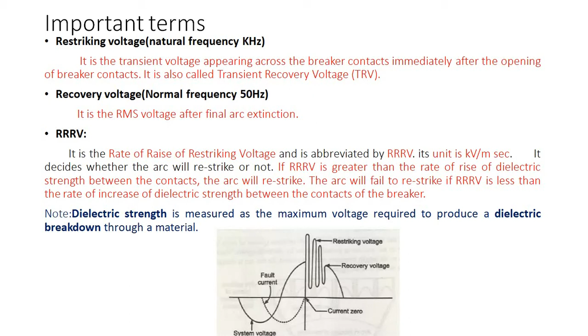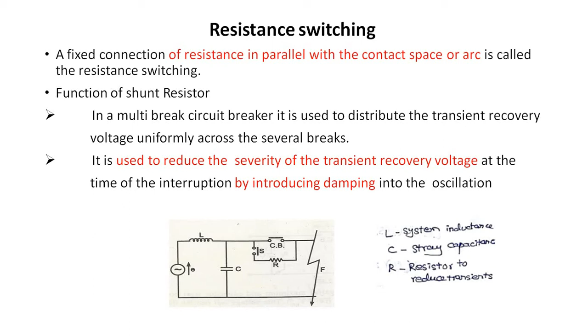Next point, resistance switching. A fixed connection of resistance in parallel with the contact space or arc is called resistance switching. Shown in the figure, the circuit breaker has a fixed contact and a moving contact, and in between, the resistance is connected in parallel. Function of the shunt resistor. The first point, in a multi-break circuit breaker, it is used to distribute the transient recovery voltage uniformly across the several breaks. Second, it is used to reduce the severity of the transient recovery voltage at the time of interruption by introducing damping into the oscillation.